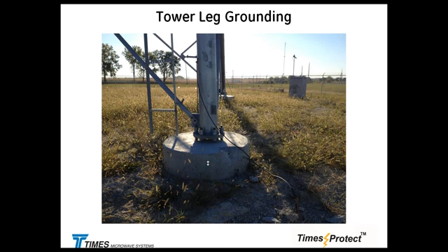So the impedance of the ufer and the whole structure was much lower than the impedance of that wire and ground rod, causing a flashover point with a huge E-field buildup. The current didn't want to go that way, and boom, it took big chunks out of the concrete. It's kind of an oxymoron: what we were trying to protect from is exactly what happened.